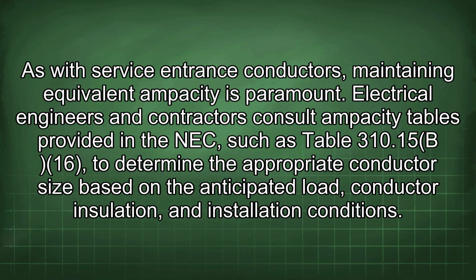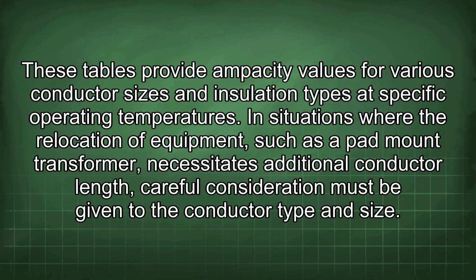As with service entrance conductors, maintaining equivalent ampacity is paramount. Electrical engineers and contractors consult ampacity tables provided in the NEC, such as Table 310.15(B)(16), to determine the appropriate conductor size based on the anticipated load, conductor insulation, and installation conditions. These tables provide ampacity values for various conductor sizes and insulation types at specific operating temperatures.